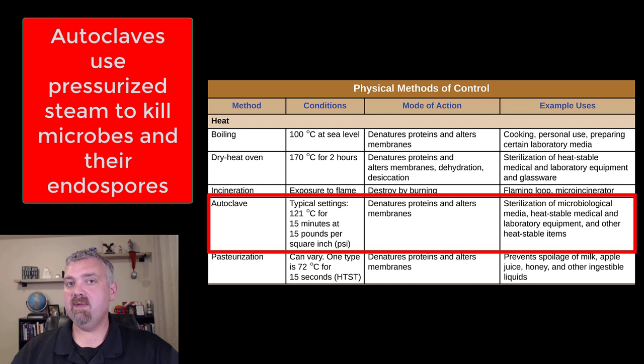The whole principle behind an autoclave is that if you increase the pressure, water boils at a higher temperature. Really key numbers I'm sure you'll be asked to know: a typical autoclave is going to boil water and turn it into steam at 121 degrees Celsius versus 100 at sea level for 15 minutes at 15 pounds per square inch. As the pressure goes up, the temperature goes up.